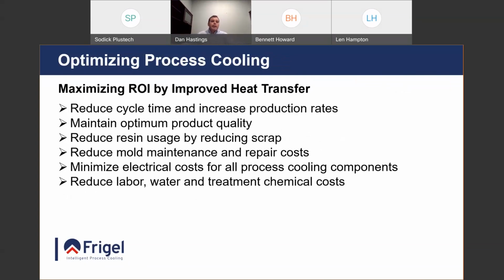Optimizing process cooling, maximizing ROI by improved heat transfer. So if we can provide good heat transfer to the mold, the best ROI we're going to get is to reduce cycle time, and be able to make more parts on that same machine in a given time. In order to reduce cycle time, we might need a larger pump for our process, which takes more energy, but as a whole, we're going to save a lot of energy by making more parts in the same amount of time.